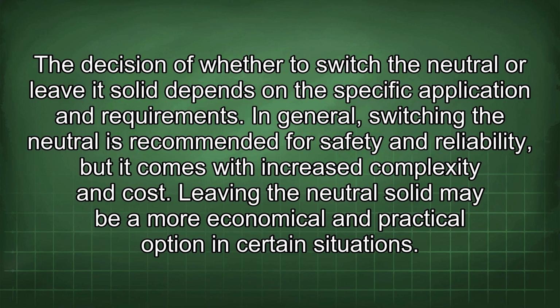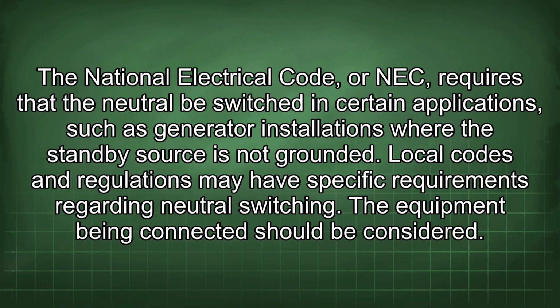and requirements. In general, switching the neutral is recommended for safety and reliability, but it comes with increased complexity and cost. Leaving the neutral solid may be a more economical and practical option in certain situations. The National Electrical Code, or NEC, requires that the neutral be switched in certain applications, such as generator installations where the standby source is not grounded. Local codes and regulations may have specific requirements regarding neutral switching.